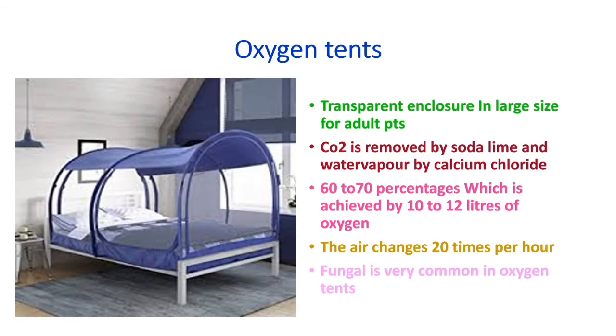Oxygen tents are transparent enclosures in large sizes for adult patients. Carbon dioxide is removed by soda lime and water vapor by calcium chloride. This oxygen tent delivers around 60–70% oxygen, achieved by 10–12 liters of O2. Air changes occur 20 times per hour, and fungal infection is very common with oxygen tents.